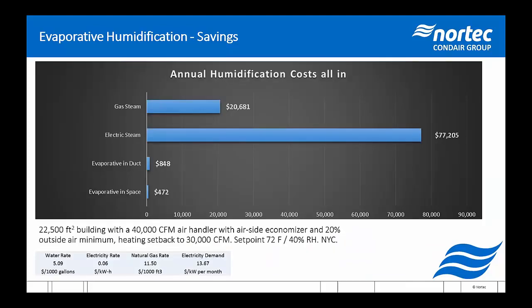So, where does this land in a real-life situation? This is annual humidification costs all in for a New York City building, fairly large, 22,000 square foot building, 40,000 CFM air handler. It's an air side economizer that only needs 20% minimum outside air. And you can see that if you were to keep that humidified with electric steam, you're charging yourself 4 times as much as gas steam, which is exponentially as much as an evaporative system. You can see the utility rates down at the bottom, and you can see all of my assumptions. If you've got questions on how I got to this, hopefully I'm about to show you step by step what we're doing.